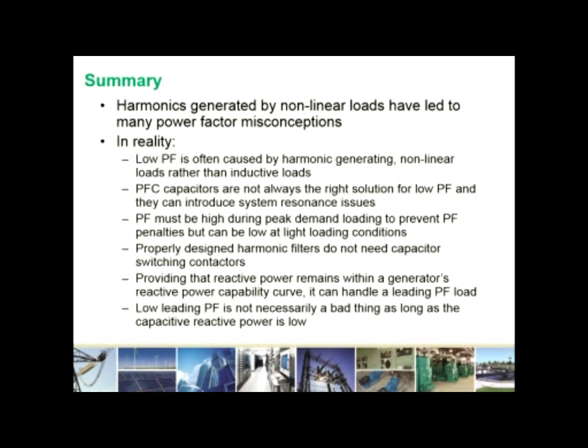So in summary then, we know now that harmonics are generated by nonlinear loads and have led to many power factor misconceptions. The reality is that low power factor is often caused by harmonic generating nonlinear loads rather than inductive loads. Power factor correction capacitors are not always the right solution for low power factor, and they can introduce system resonance issues. Power factor must be high during peak demand loading to prevent power factor penalties, but can be low at light loading conditions. And properly designed harmonic filters do not need capacitor switching contactors.